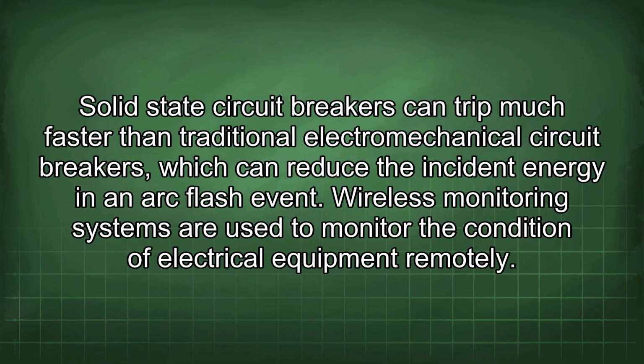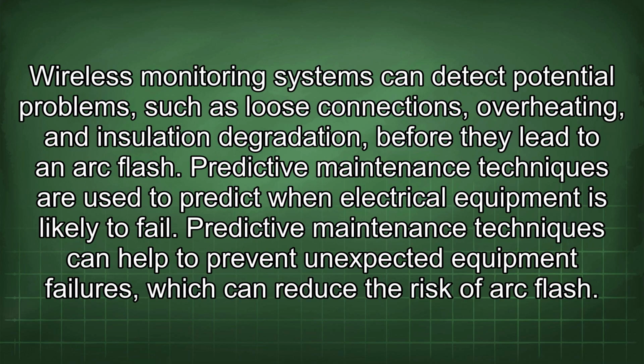Wireless monitoring systems are used to monitor the condition of electrical equipment remotely. Wireless monitoring systems can detect potential problems such as loose connections, overheating, and insulation degradation before they lead to an arc flash. Predictive maintenance techniques are used to predict when electrical equipment is likely to fail. Predictive maintenance techniques can help to prevent unexpected equipment failures, which can reduce the risk of arc flash.